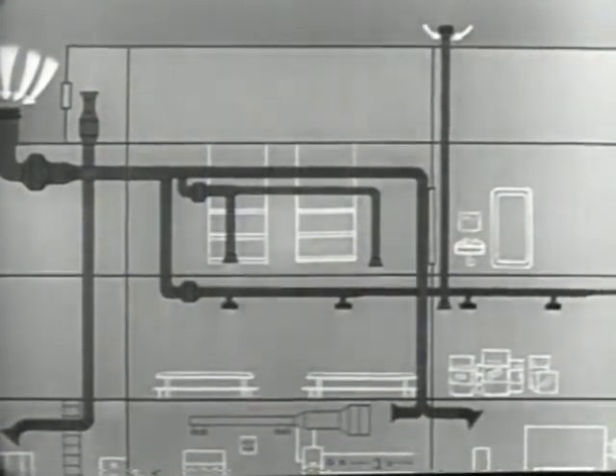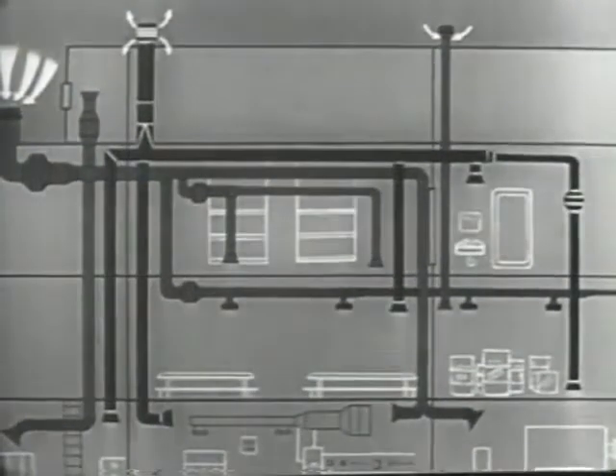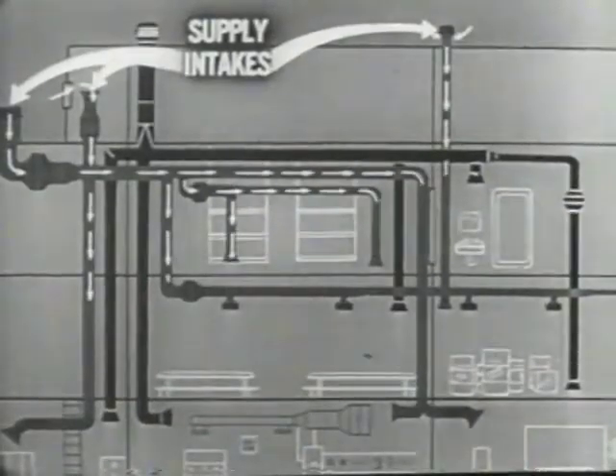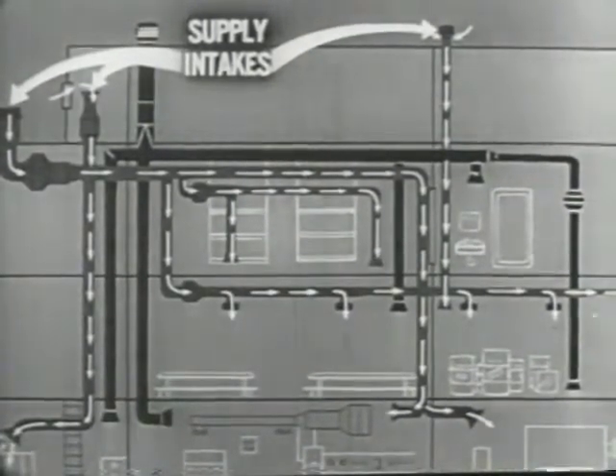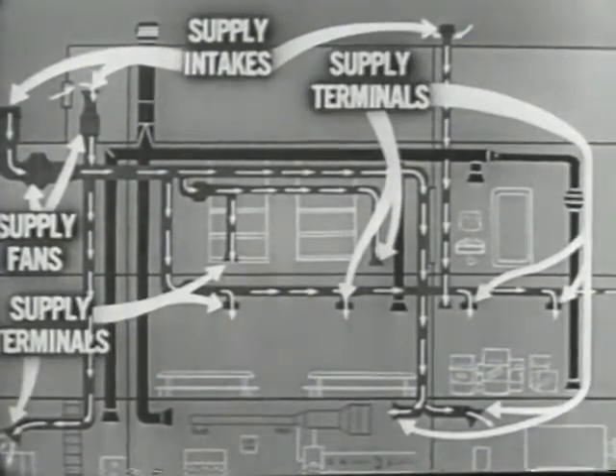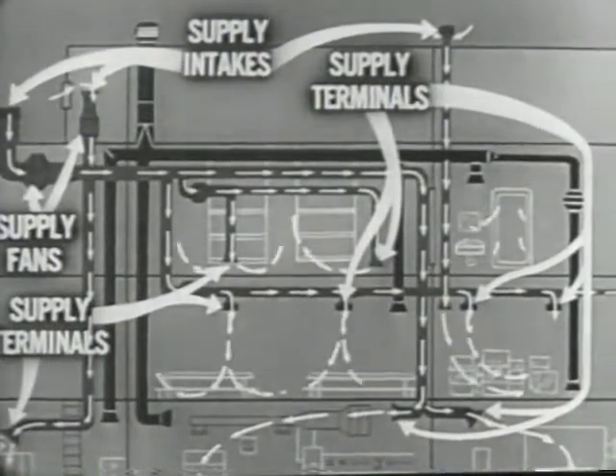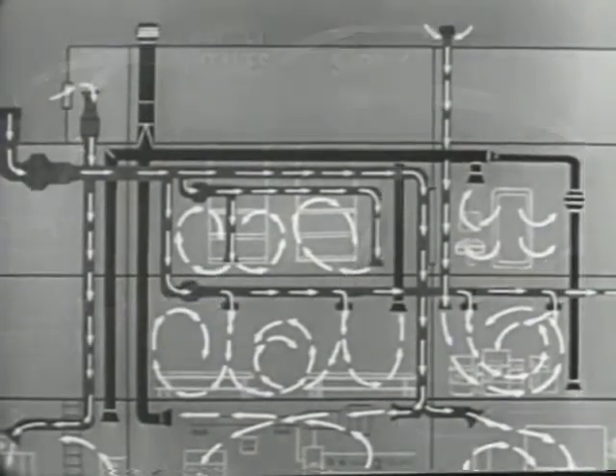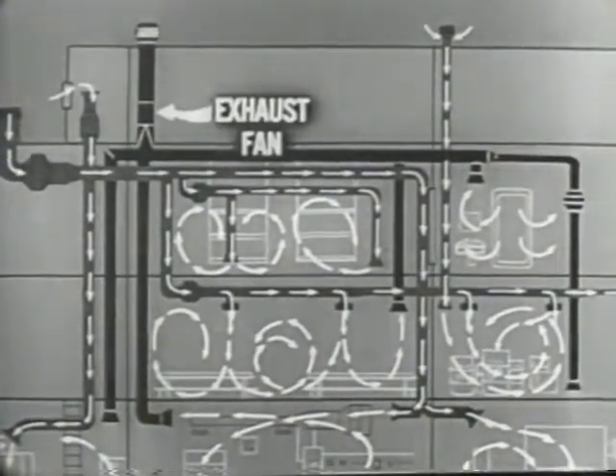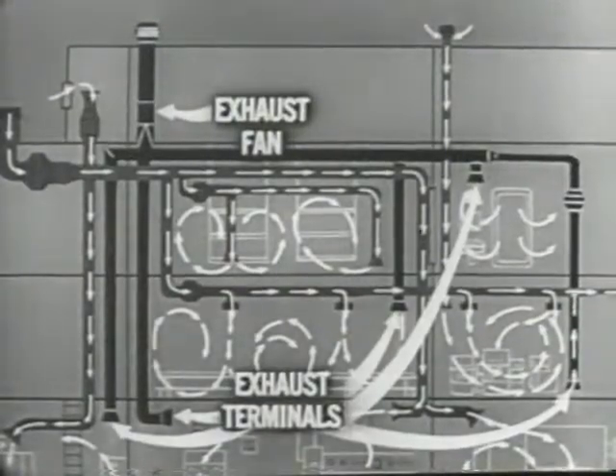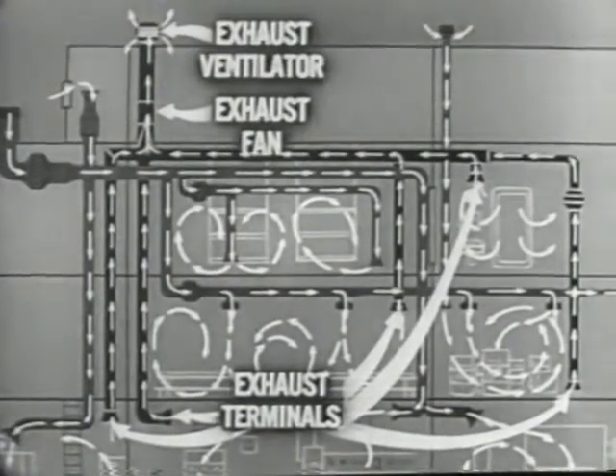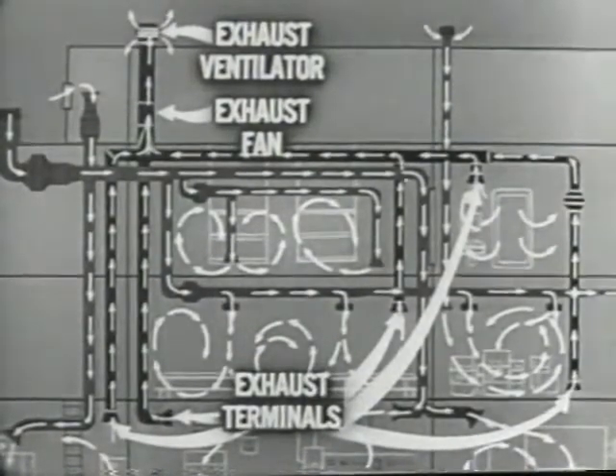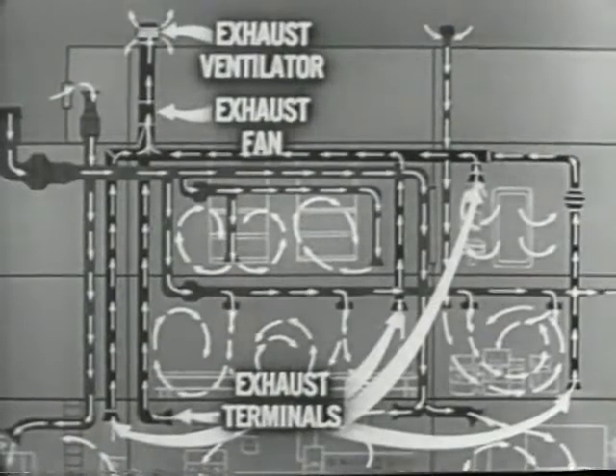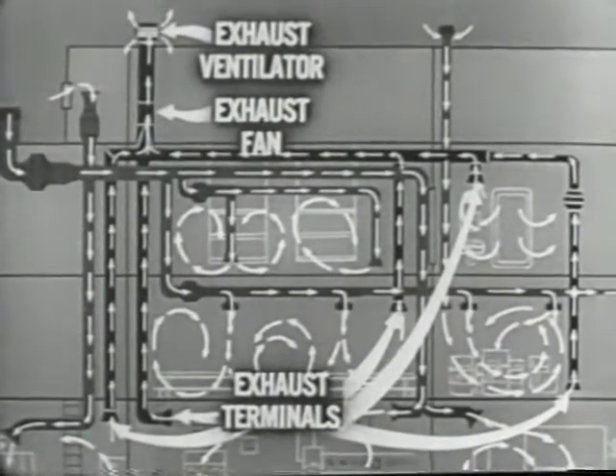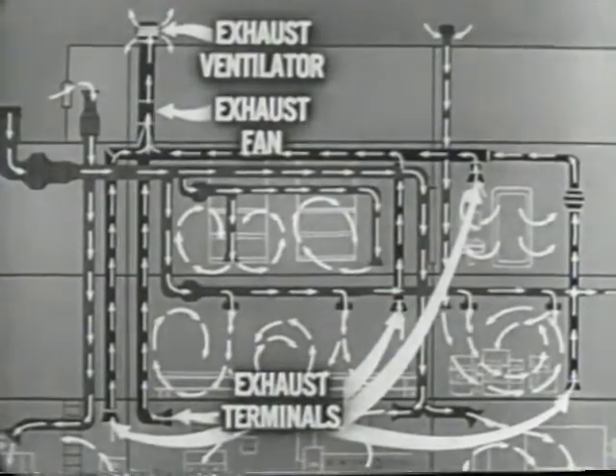In a typical ventilation system, outside air is conducted to and from below-deck spaces through a network of ducts. Air enters through ventilators or deckhouse openings. It is forced through the ducts by fans, delivered through a series of supply terminals, and circulated through individual spaces where it takes out heat, moisture, fumes, and odors. Exhaust fans draw the warm, used air through the exhaust terminals and ducts, then discharge it through exhaust ventilators or deckhouse openings to the outside. Exhaust outlets are provided in the spaces having supply outlets, or are located in water closet spaces, pantries, and passageways adjacent to those spaces.